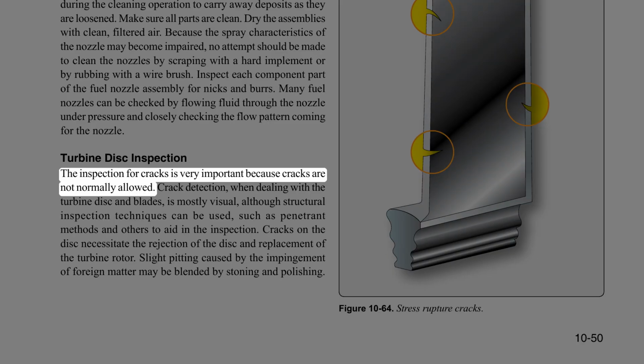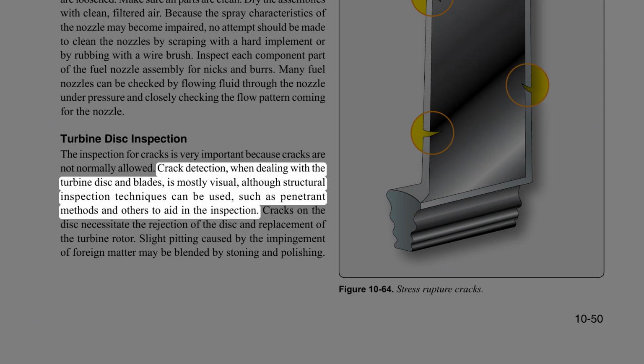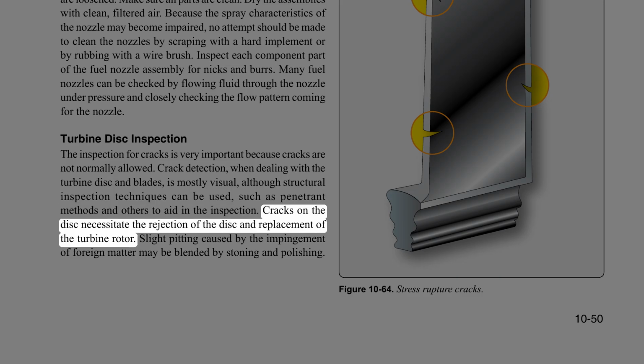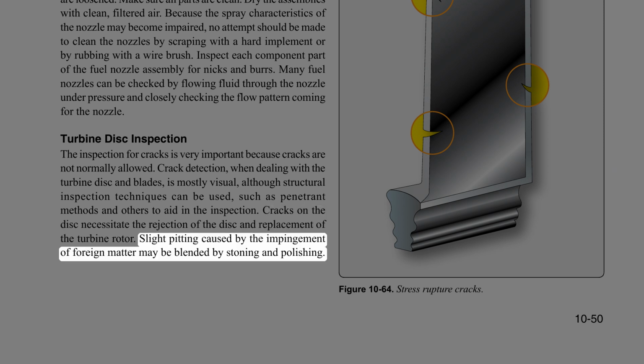The inspection for cracks is very important because cracks are not normally allowed. Crack detection, when dealing with the turbine disc and blades, is mostly visual, although structural inspection techniques can be used, such as penetrant methods and others to aid in the inspection. Cracks on the disc necessitate the rejection of the disc and replacement of the turbine rotor. Slight pitting caused by the impingement of foreign matter may be blended by stoning and polishing.